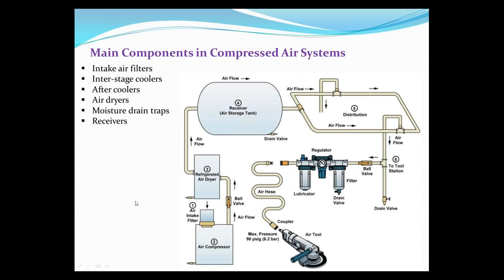Then the next important component is the receiver or storage tank. Then your distribution network, and drain valves are also fitted before your load. You can have drain valves or a lubricator separator. If your compressor is the flooded oil type, then you can install oil removal filters. After the filter it goes to your air tool or point of application. So this is the simple network of a compressor system.